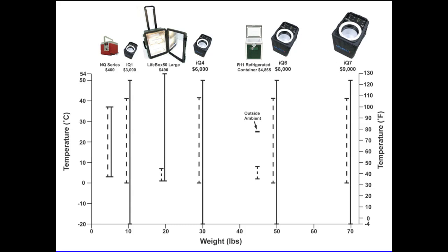Here are some commercially available products that could protect point-of-care in these extreme conditions. The x-axis shows the weight of the devices, so as you move from left to right, the devices become progressively heavier. The y-axes show temperature ranges that correspond with the dotted and solid lines under each device. The dotted lines show the temperature range that each device can hold internally. The solid lines show the temperature range that each device can handle from the outside environment while still keeping the internal temperature within the corresponding dotted line. As an example, let's look at R11, or the device third from the right. This device has only been tested at a constant outside temperature of 25 degrees Celsius, during which the container was able to hold 2 to 8 degrees Celsius internally for an extended period. If you would like more explanation of this figure, please comment below and we will try to help. Please feel free to ask questions about anything else in this lecture as well.